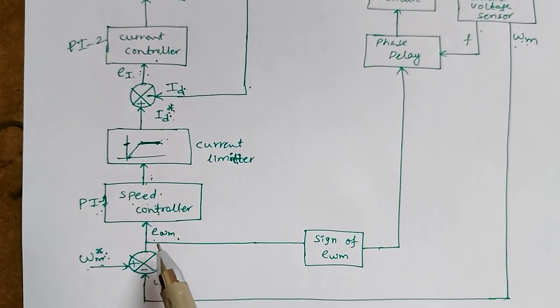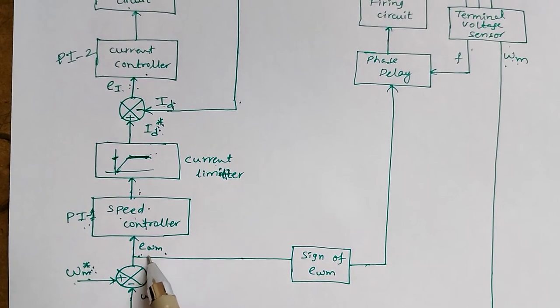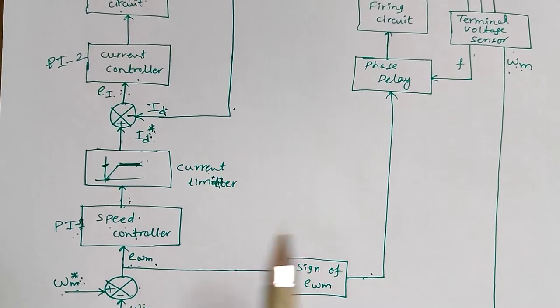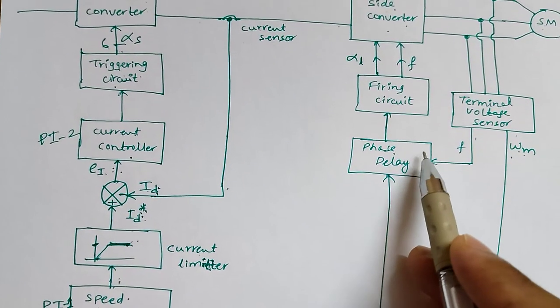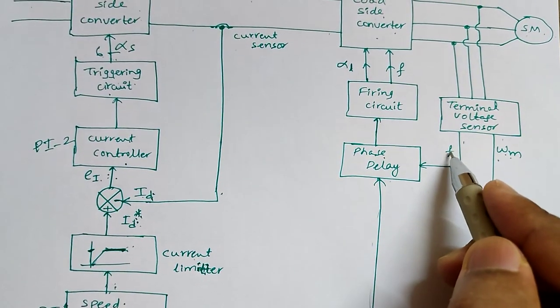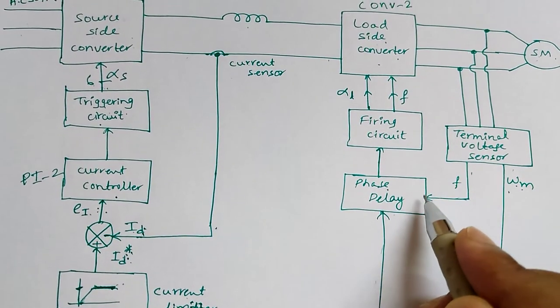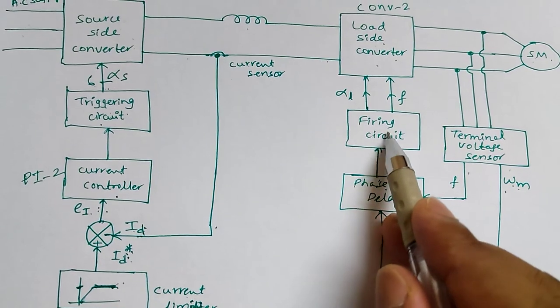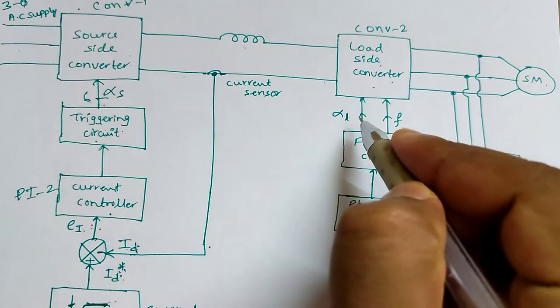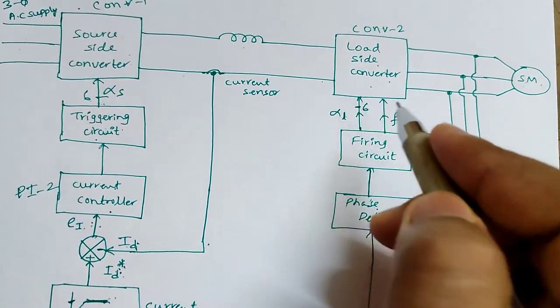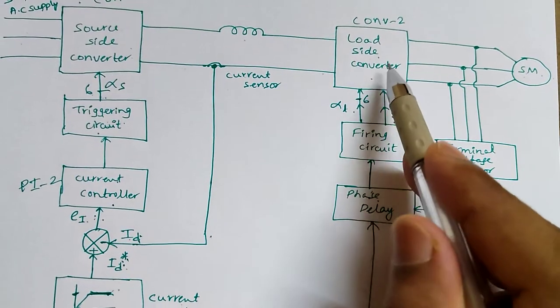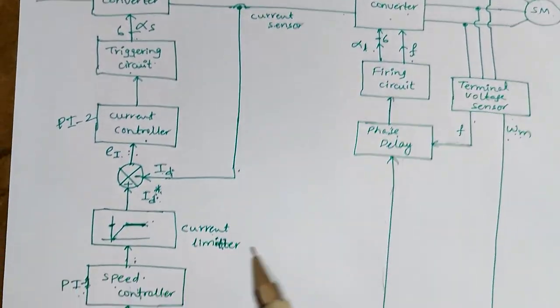To obtain the firing pulses for the load side converter, the rotor angle EΩm is passed through a sign function, giving 180-degree phase displacement. This is then passed through a phase delay block, which provides a delay for the frequency and the sine of EΩm, since the frequency should not change instantaneously. That output is given to the firing circuit of the load side converter, which also generates six firing pulses. These firing pulses, along with the required frequency, are given to the load side converter to operate it in the required speed range.